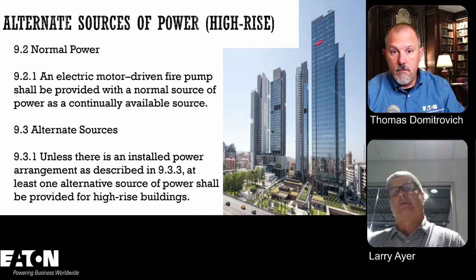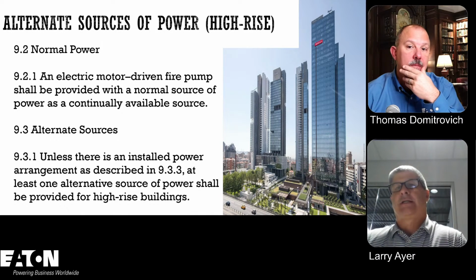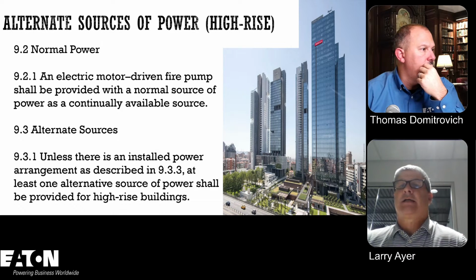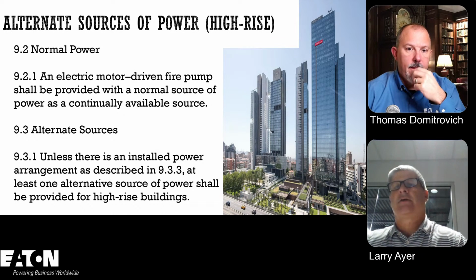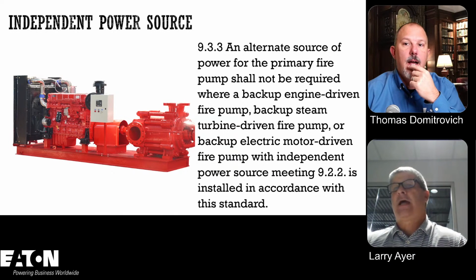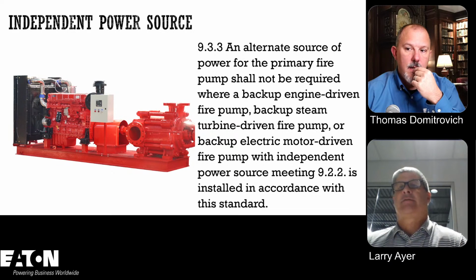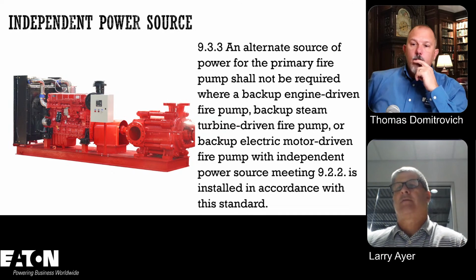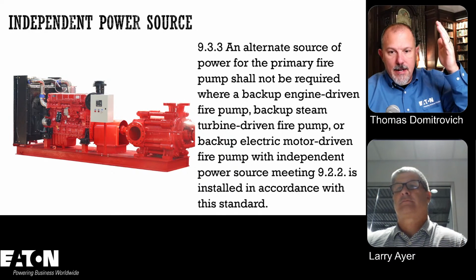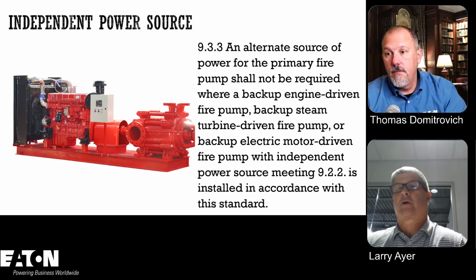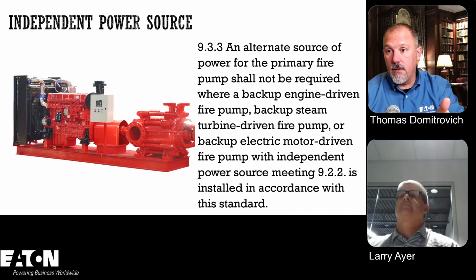Correct. So the first thing is 9.2.1 says you've got to have a normal source and it's got to be continuously available. And then it goes on from there, and I skipped a couple of things, but 9.3 says, unless there's an installed power arrangement as described in 9.3.3, at least one alternate source of power shall be provided for high-rise buildings. Now, 9.3.3 talks about the engine-driven fire pump. So if you have that, you don't need an alternate source of power for a high-rise. But if you have your utility service coming in, you always need an alternate source of power for a high-rise. Okay, so if I'm in a high-rise, I'm always going to have an alternate source of power unless I use this. Correct. If I use this, then this could be my only source of power. Correct. All right.